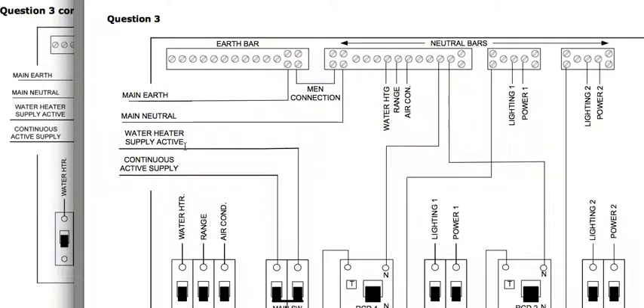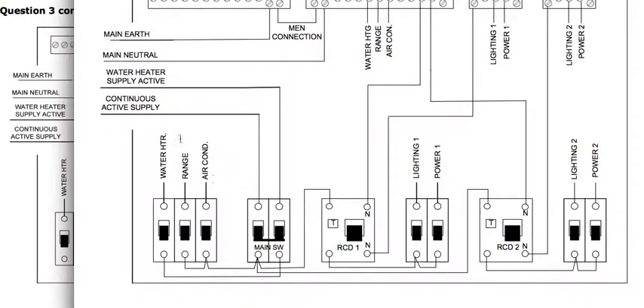We've got the water heater supply coming in, and that's coming to our main switch, and also the continuous supply to our main switch. The water is feeding through the main switch, through there, up to our water heater. So that would be a separately switched and protected supply. The continuous active supply again comes to our main switch, and then our main switch will feed our air conditioning and our range, and it will also feed our 2 RCDs.